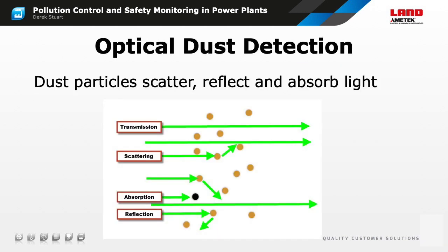There are several ways for us to detect the low levels of dust that are emitted from a modern power plant. Most of these depend on the interaction between light and the particles in the flue gas. There are several types of interaction, and the strength of each depends on the concentration of the particles. Traditionally, we've measured the amount of light transmitted using an opacity monitor. More recently, instruments have employed some form of light scattering. Forward, side, and back scattering are all used. In this illustration, the back scattering is shown as reflection, which is essentially the same thing. No matter which sensing technique is used, the sensor does not measure the dust concentration directly, but measures a parameter related to that concentration.